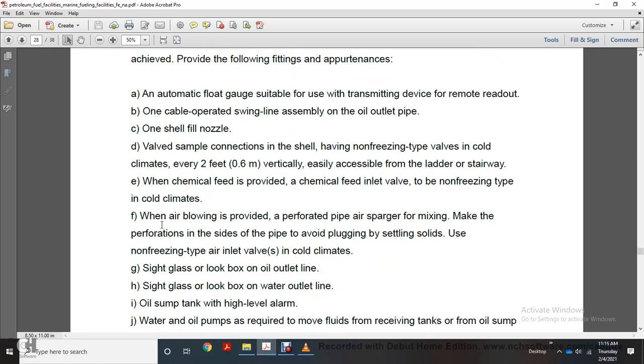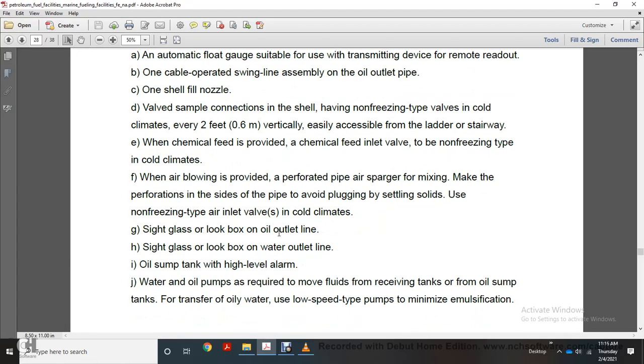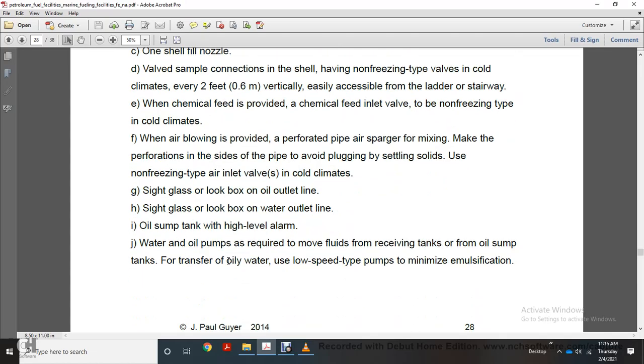When air blowing is provided, use a perforated pipe air sparger, making the perforations on the side of the pipe to avoid plugging with settling solids. Use a non-freezing type air inlet valve in cold climates. Provide a sight glass or look box on the oil outlet line, a second sight glass or look box on the water outlet line, and an oil sump tank high level alarm.